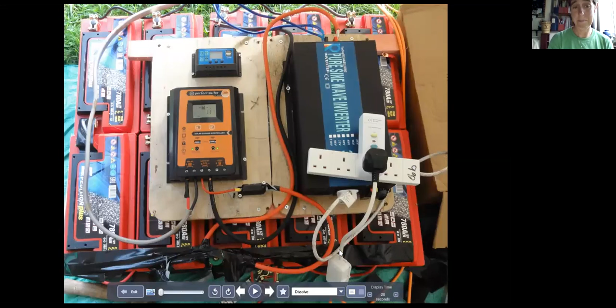This is the storage batteries for the new 2 kilowatt system, about 10 kilowatt hours worth there. And that's a sine wave inverter, which goes up to about 5 kilowatts peak. But it's interesting in that it's got a center tapped output, so if you ground the center tap of the output, it means your maximum voltage to earth is only half the normal mains voltage. So it's 110 or 115, which is the sort of approach used on building sites to improve safety.